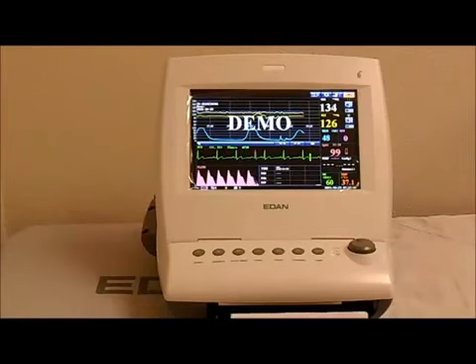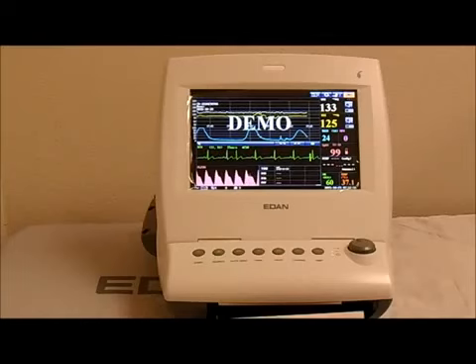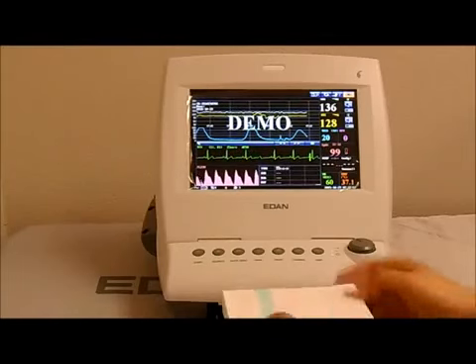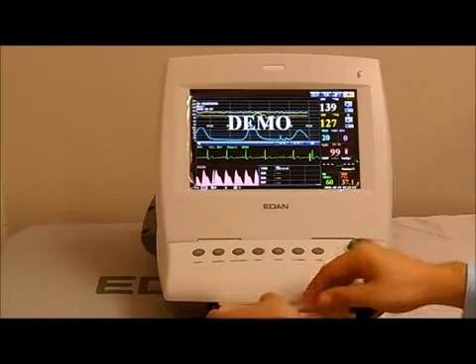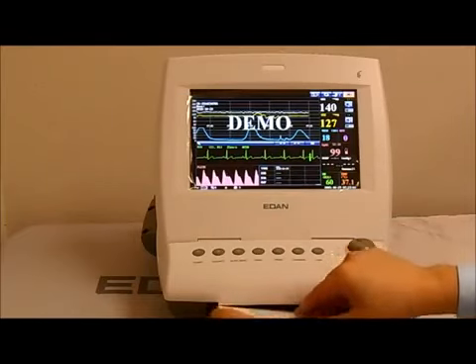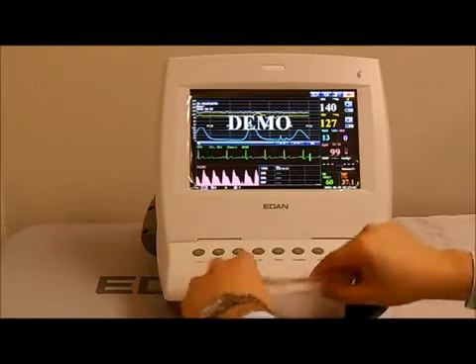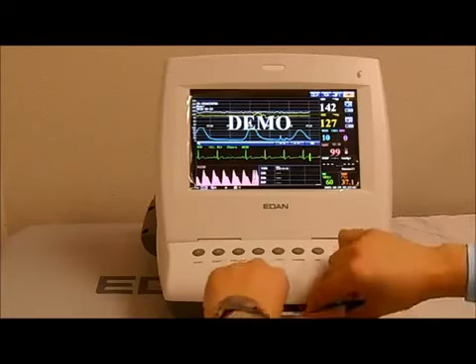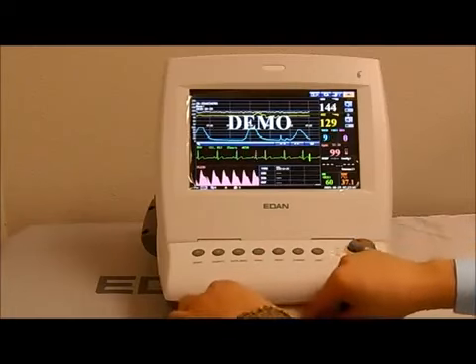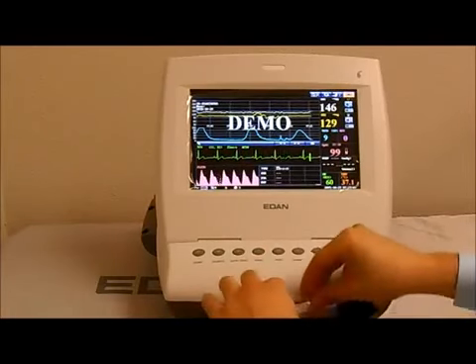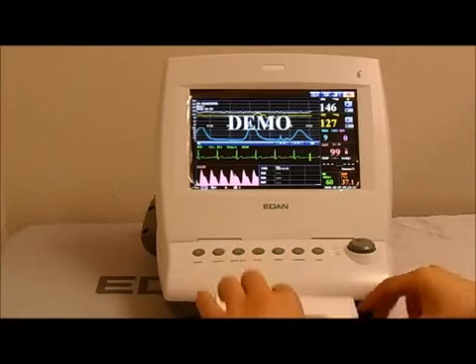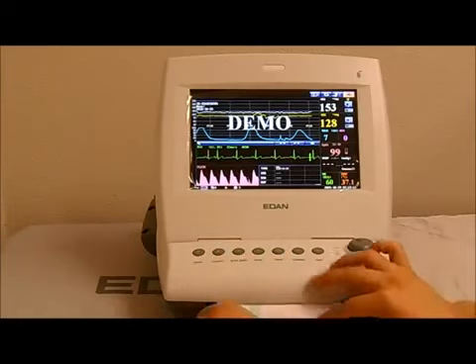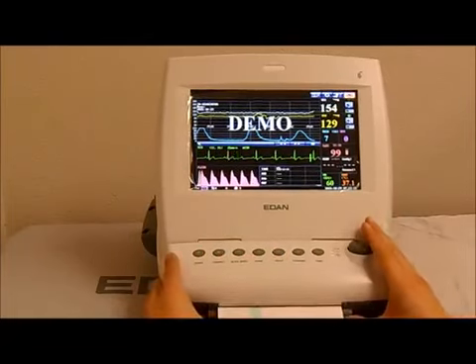The CTG or the TOCO has to be on the right. So on the left, the grid should be going from 30 to 240, and on the right, it's 0 to 100. So you load the paper with the grid facing up. You want to make sure it's nice and centered. And then you take one sheet and you prop it over the roller, and now you can close the compartment.